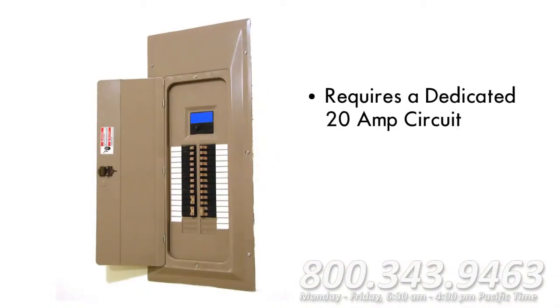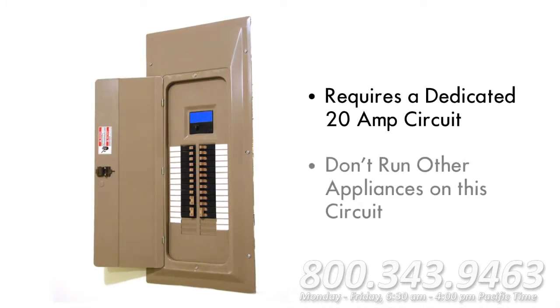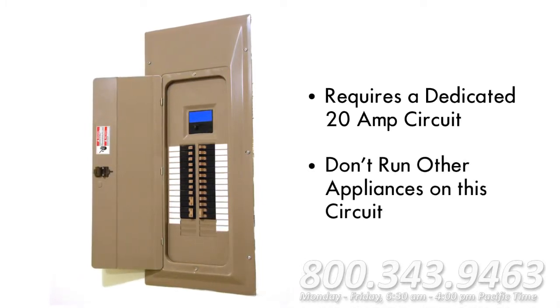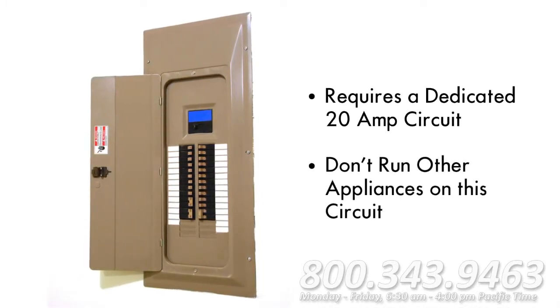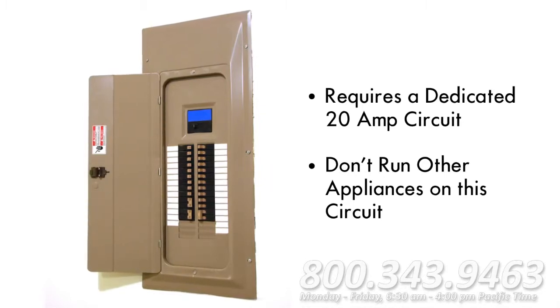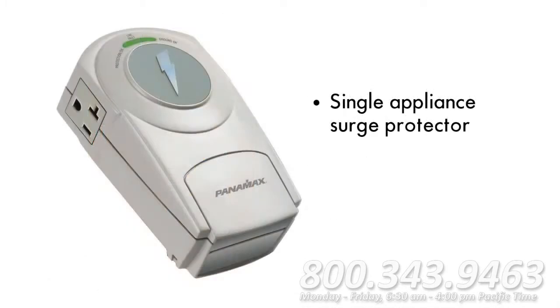Make sure that you did not connect your unit to a GFI. Also, if you didn't wire in a dedicated 20 amp circuit for your cooling unit, it may not be able to draw enough electricity to power the unit. Unplug any appliances that might be on the same circuit and make sure you have a dedicated circuit installed as soon as possible. For added protection, you should run the unit through a single appliance surge protector, like this one.